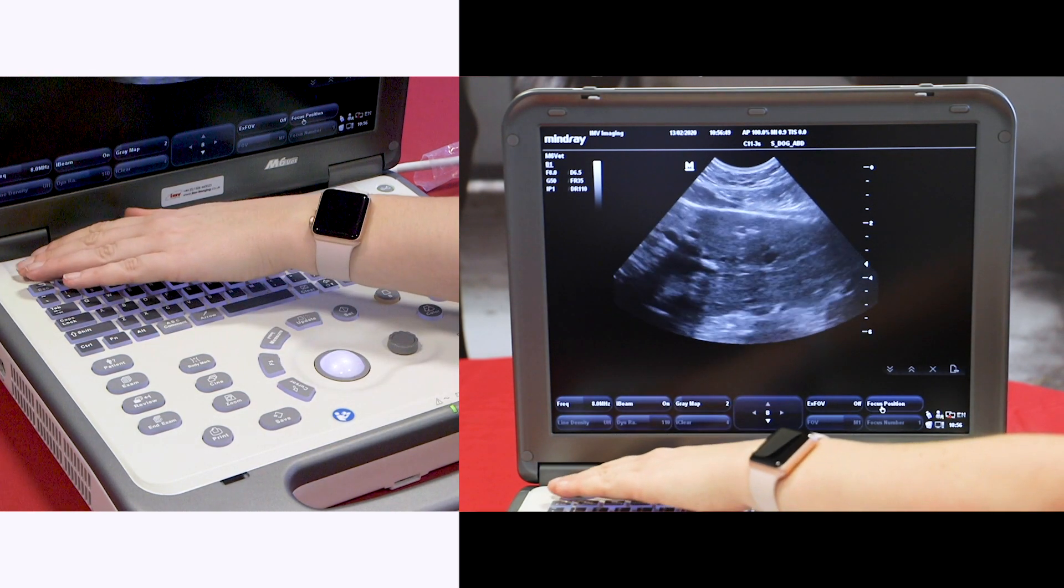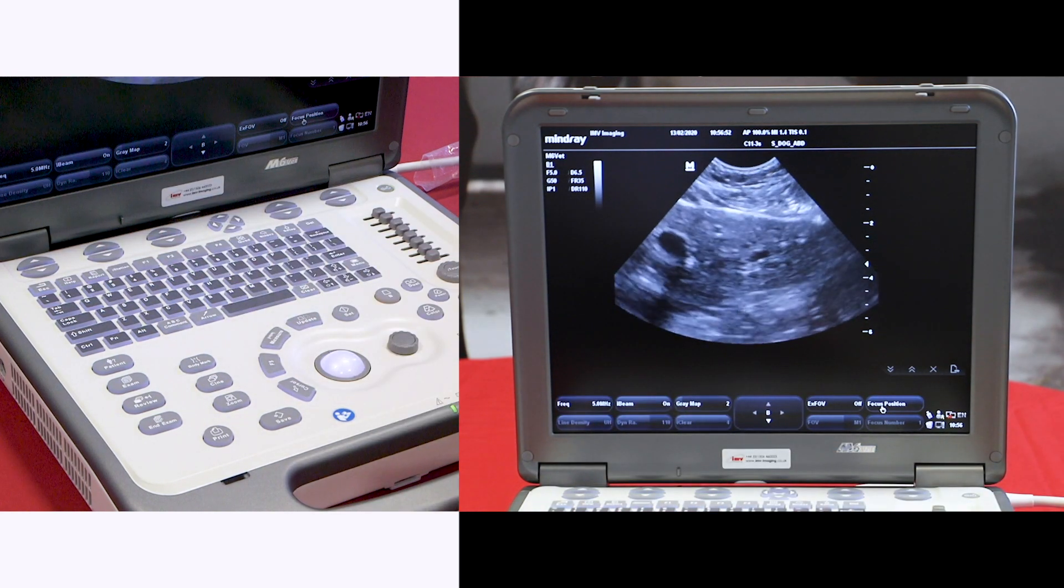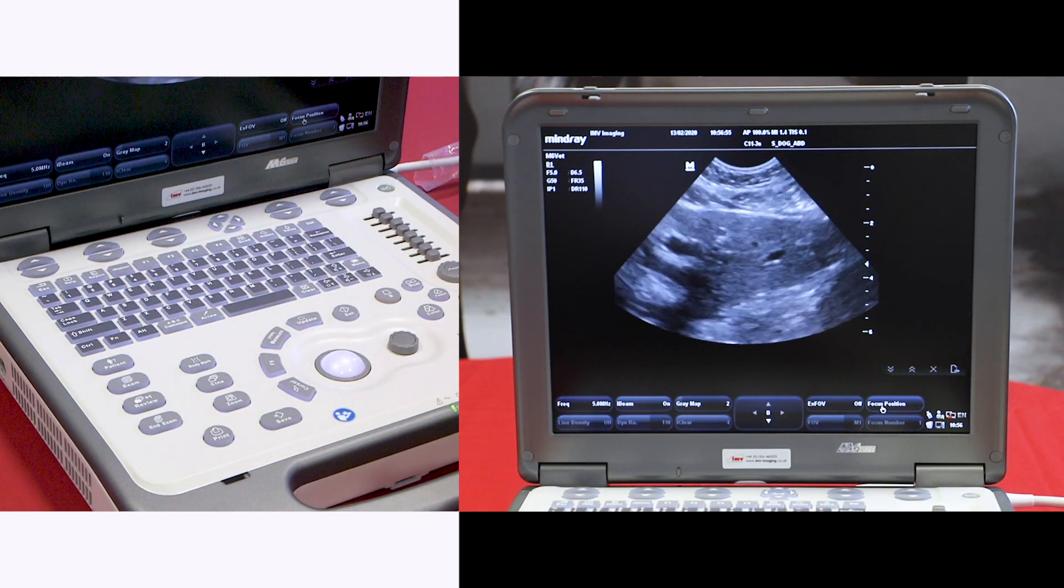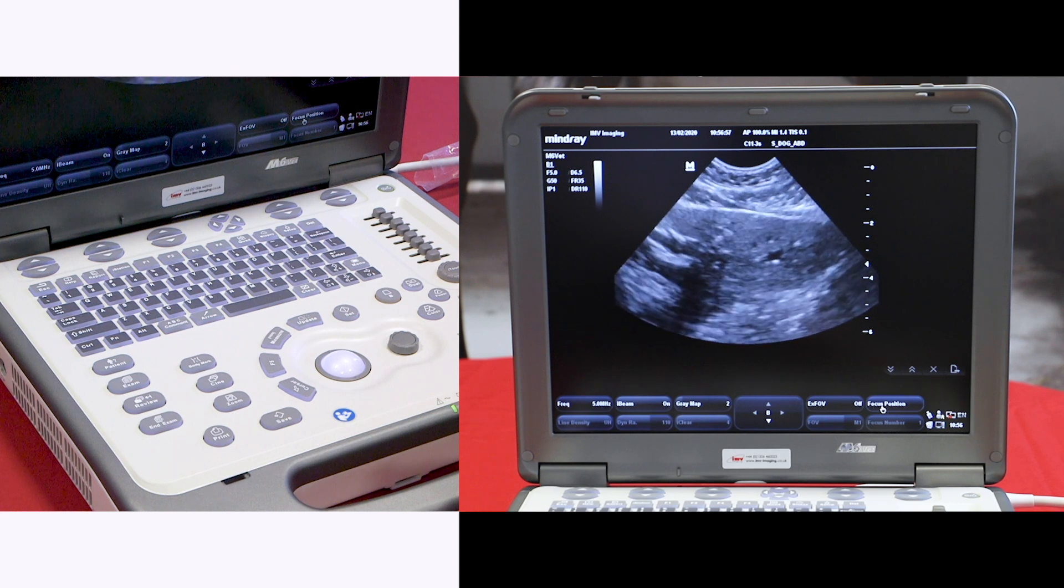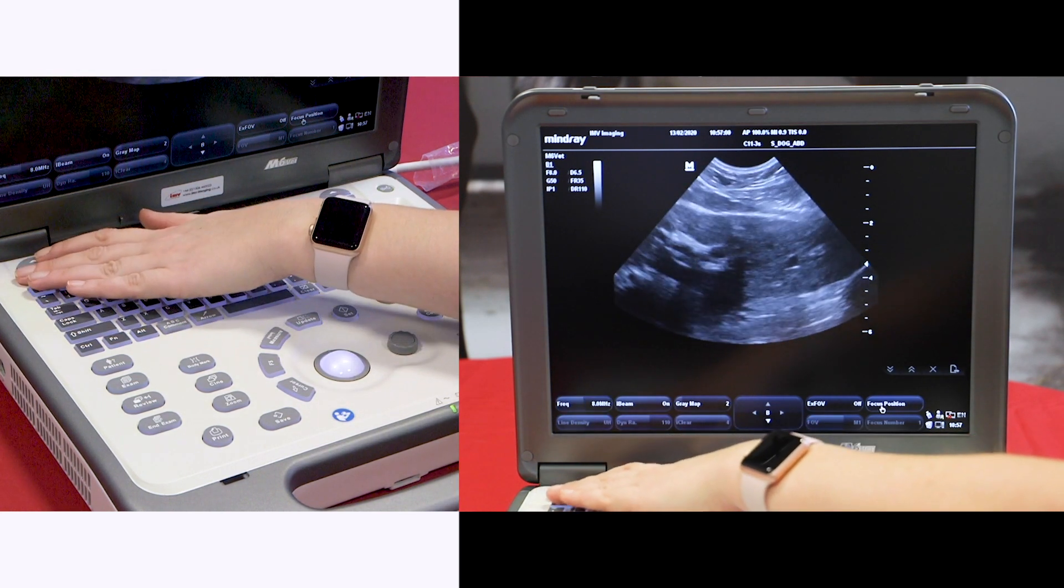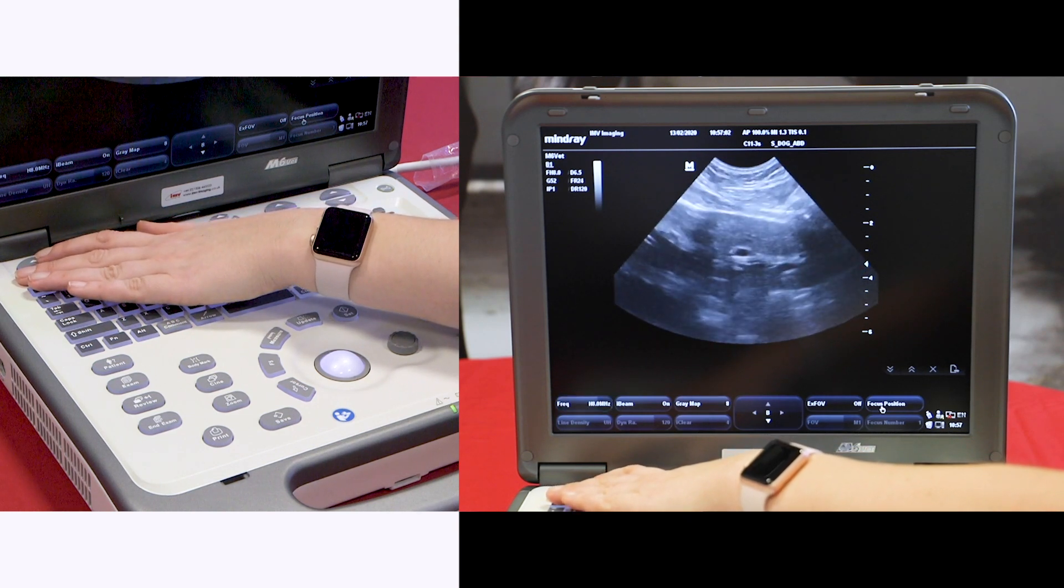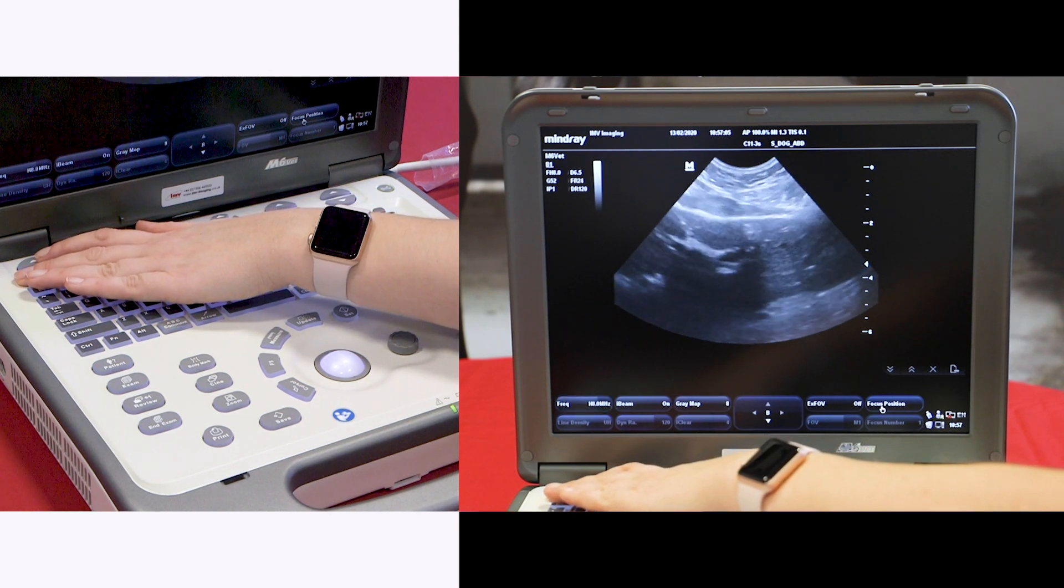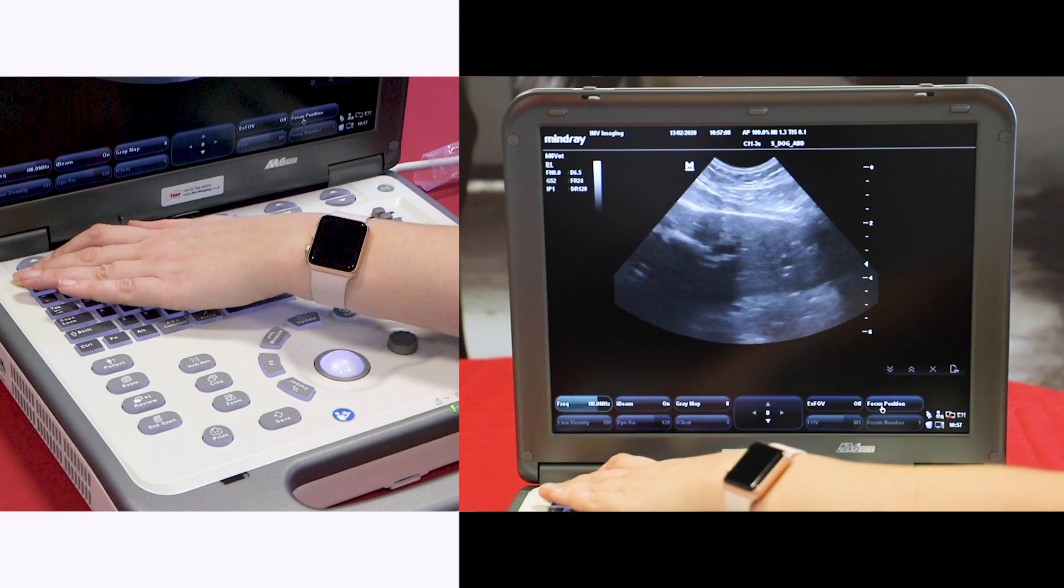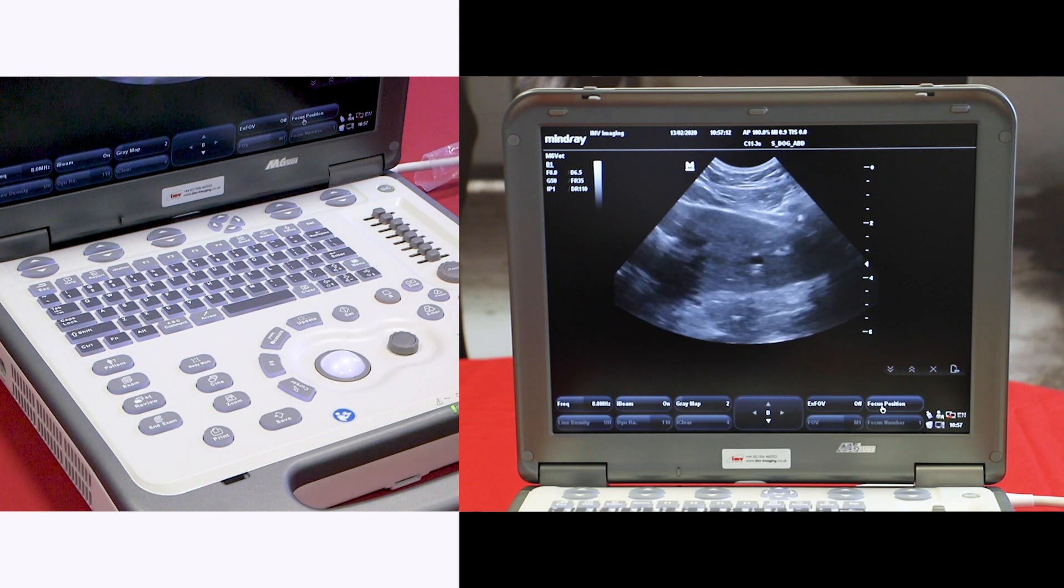If you go lower the image quality is a bit poorer but we would get further penetration if we were imaging deeper. If you go higher than the normal frequencies you can go on to harmonic frequencies. This will give you a slightly different image. It's personal preference whether you like to keep it like this or go back down to your normal frequencies.